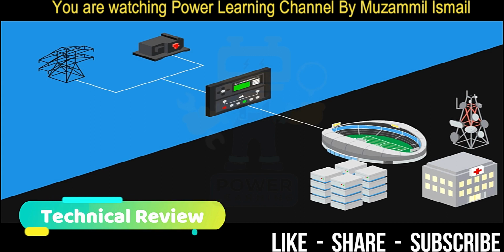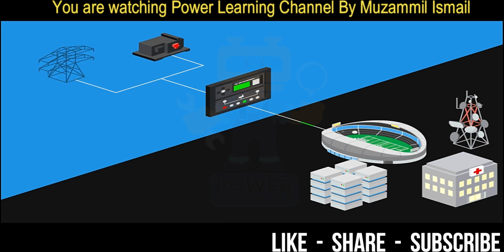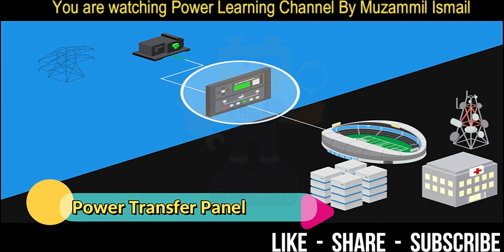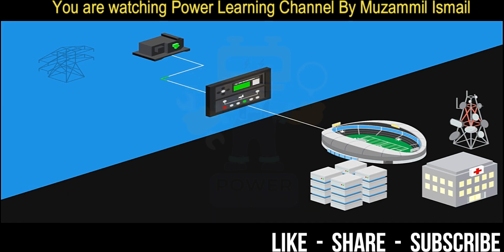As you see on the screen, this is the animated view of a single line diagram of an ATS system. There is a power source incoming from the transformer and there is one generator, and there is also one digital controller installed between these two sources, which senses the supply of the generator and the mains power. So in all standby sites where we use this in industry, as you see in the animation, there is a stadium, a hospital, a building, a telecom site. All these applications use standby generators.